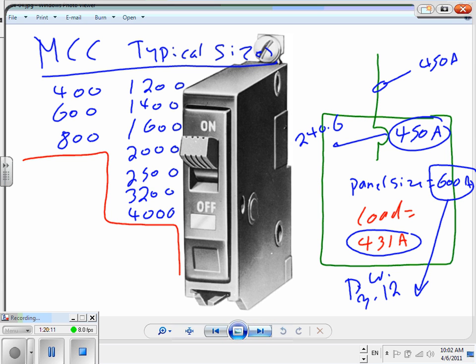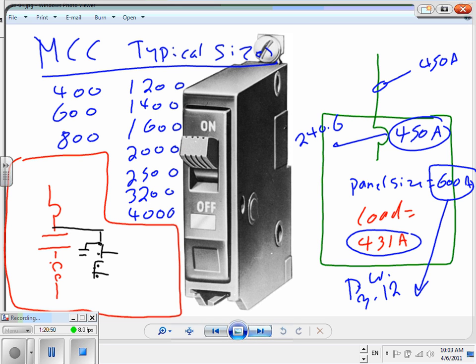Here's what an MCC has that a panel doesn't have. You guys remember the overcurrent detection device? You remember the controller? Remember the overload? And what else do we have? No, this is not an overload, Chad. The overload, there you go. So I have the overcurrent detection device, the controller, the overload. Am I missing something here? And from here, I'm just going to show quick, guys, the control circuit, the push buttons. You remember the push button start and the push button stop. All these, and the contacts across these, and the low voltage. I mean the overload.